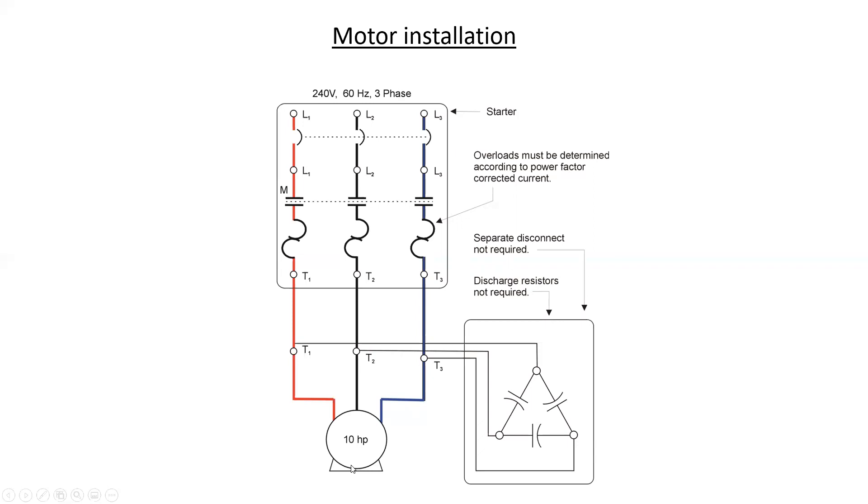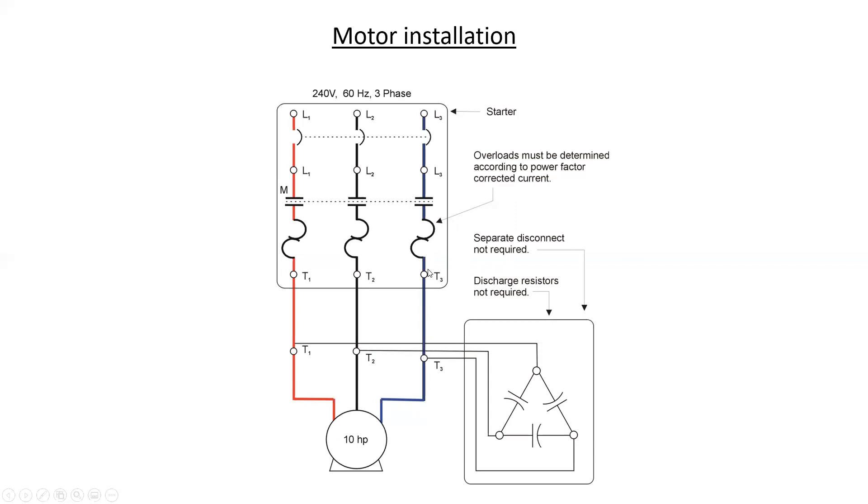Now this also has an effect on the overload sizing. Remember from Section 28 that the overloads are based on the full load amps of the motor. Because of that, if the capacitors are connected right here, the full load amps of the motor will only be present from the point of the capacitor down to the motor. From here up will be the power factor corrected current, which is lower, always lower. And due to that, the overloads will have to be sized to that lower current value.